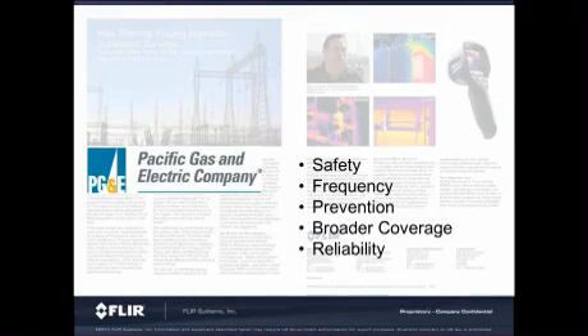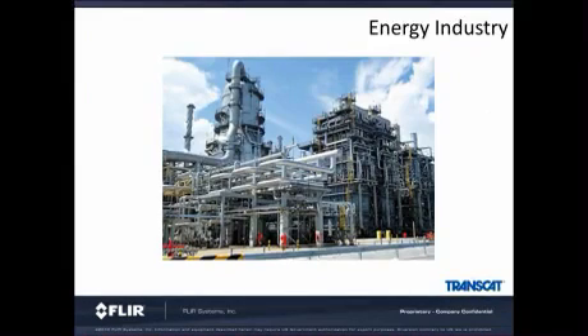In one case, an electrician found the failing transformer. In general, the cost for replacement could be anywhere between $1.8 and $8 million. In this case, it was $3 million. The radiator was clogged and there was no oil flow. The repairs were immediately scheduled, saving $2.7 million and taking about 1/6 of the time to repair compared to installing a new transformer. This is a nice example of how a thermal imaging program paid for itself with one find.